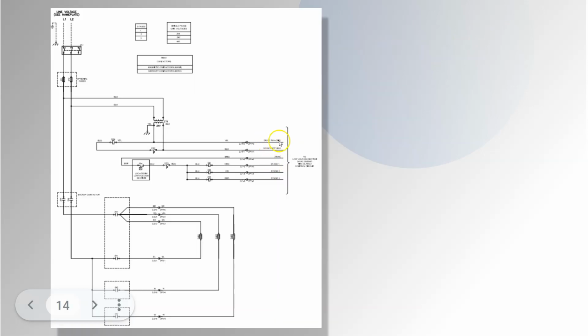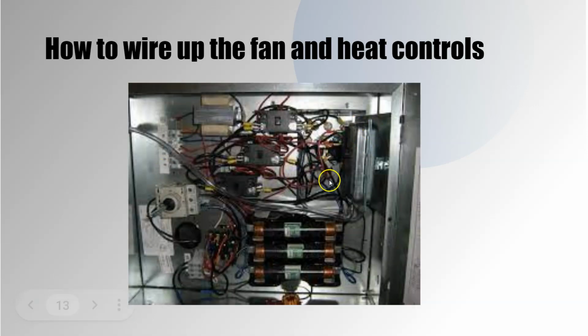So the top line is our neutral coming off our 24 volt transformer. So it's 24 volts neutral. The next one is 24 volts hot. And that's what we're getting from the transformer right here. And then what we have here is 24 volts going out to the relays, the contactors for the stage 1, stage 2, and stage 3 heat. And what we'll do from here, we'll fire a neutral or a common out to close this contactor. Now the hot has to go through an air proving switch, which is this silver guy right here, which has tubes going to it. So it has to prove airflow for electric heat to come on.